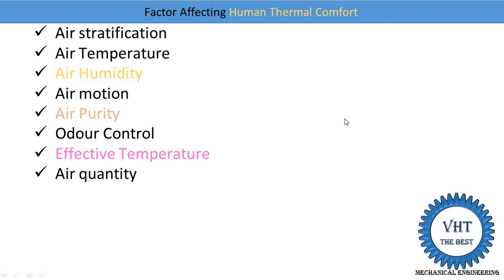The next factor is air quantity. It is essential to decide the percentage of recirculated air and the amount of outdoor air in an air conditioning system. Generally, in a central air conditioning system, 15 percent of fresh outdoor air is supplied to maintain the oxygen level and dilute carbon dioxide. Our human body rejects CO2, and if fresh air is not supplied, the CO2 level increases and we feel uncomfortable. So 15 percent fresh air is required to be supplied in air conditioning systems.